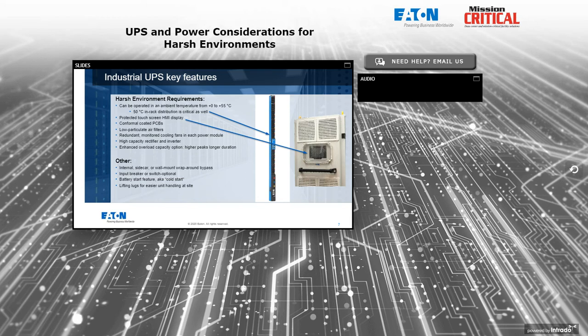Input circuit breakers or switch contactors may be standard or optional. It's become relatively common in the IT business to eliminate the input breaker and just use fuses and contactors, recognizing that there's typically an input breaker on the wall beside the UPS. But in industrial applications, you're more likely to see a request for the input breaker and output breaker, for that matter, to be internal to the UPS, even if it's redundant to external breakers the client may have.